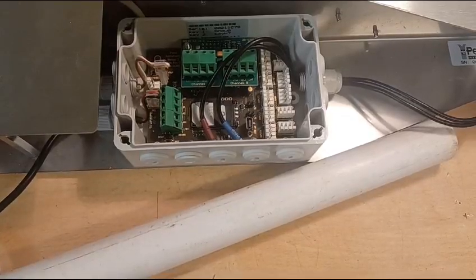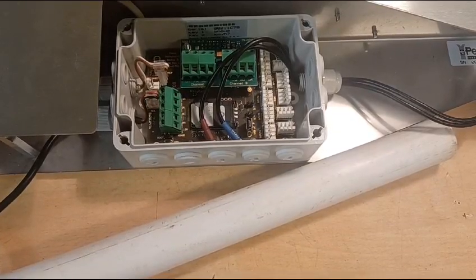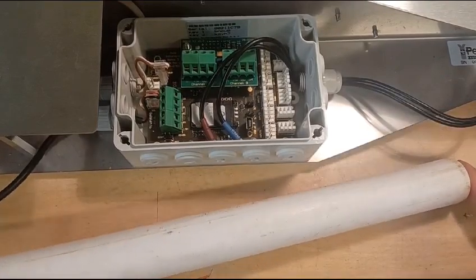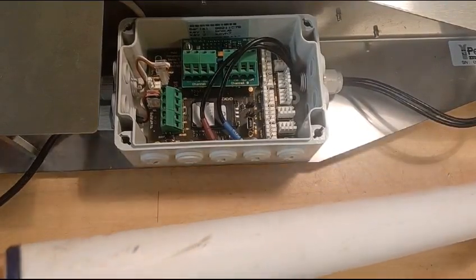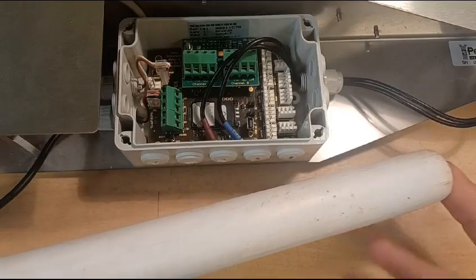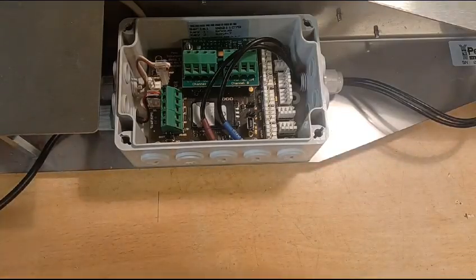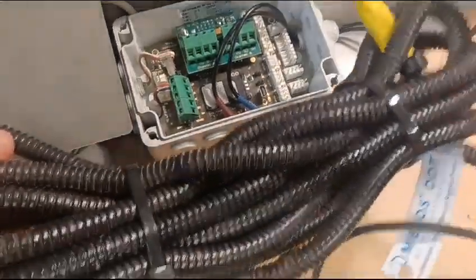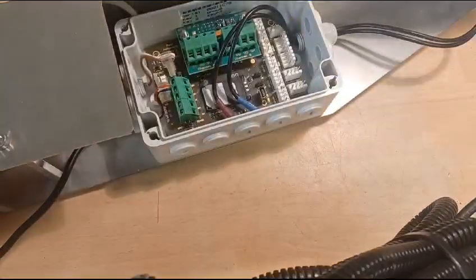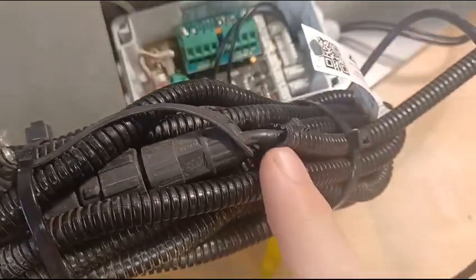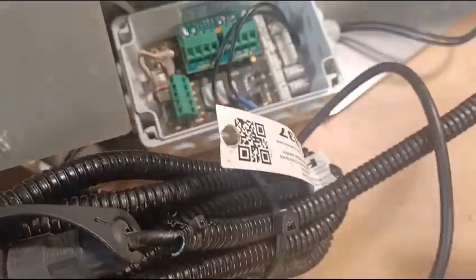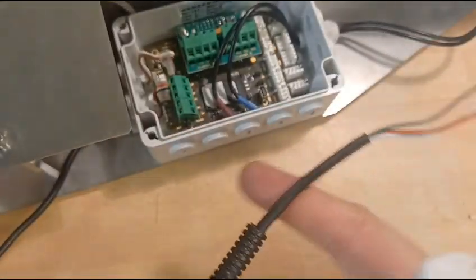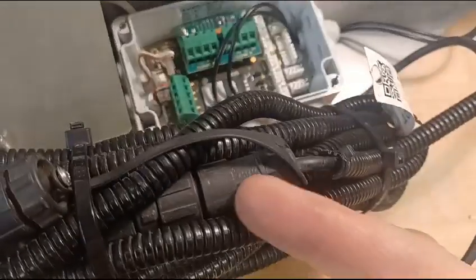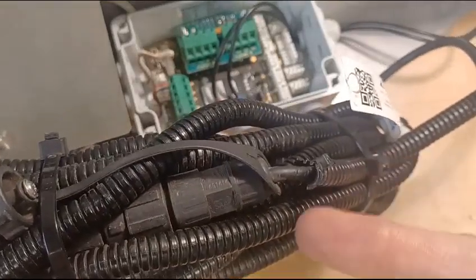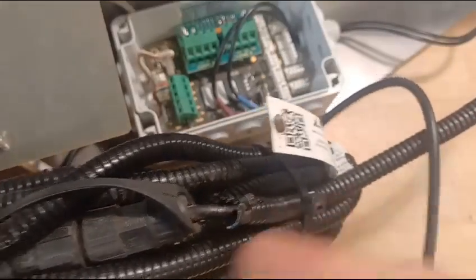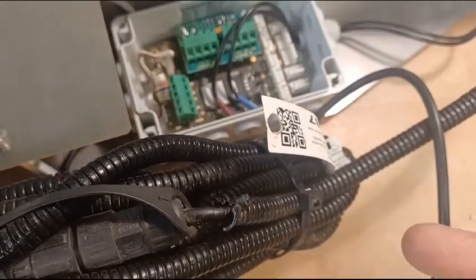Installing a moisture probe on an ATS22, we generally use 30 or 60 centimeters. I've got a test 30 centimeter one. Comes with quite a long cable, which I've got wrapped up because of space. There is a connector block here, which this part is the tail that goes into the ATS22, and the rest of it goes to the probe itself. So you can leave the tail connected and replace just the probe and cable.